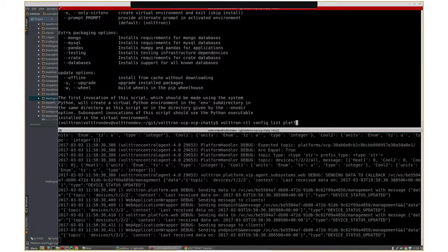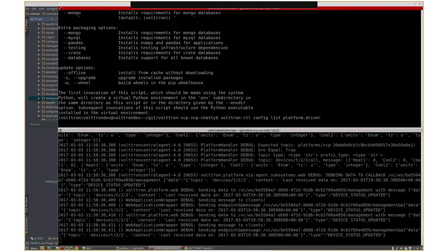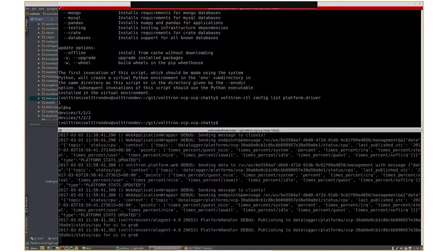Typically, what you're going to do in practice is break it up into logical devices. You're going to point multiple drivers at the physical device, and each one's going to grab a piece of that thing based on the actual stuff in your HVAC system that it corresponds to. And since the setting is basically a global setting for how it tells the drivers when to scrape, you could spread that one physical device over logical devices, and then spread out the scraping of that device into smaller requests just by virtue of the fact that you've broken it into logical devices by setting up multiple drivers. Does that make sense?